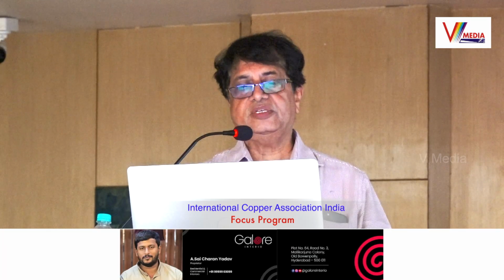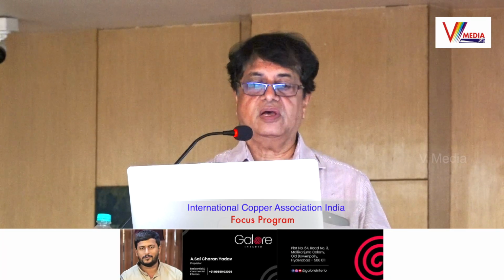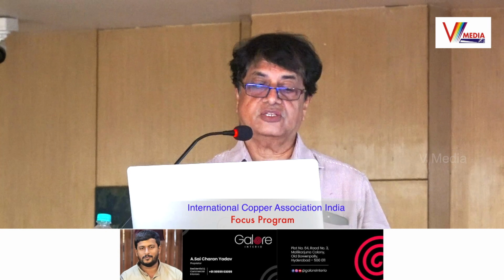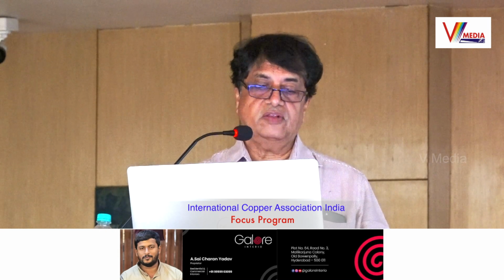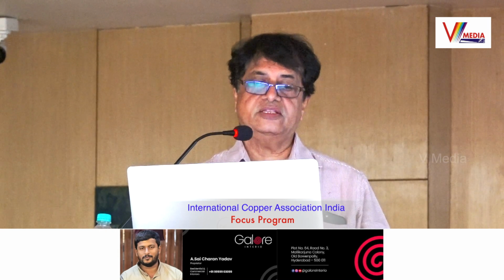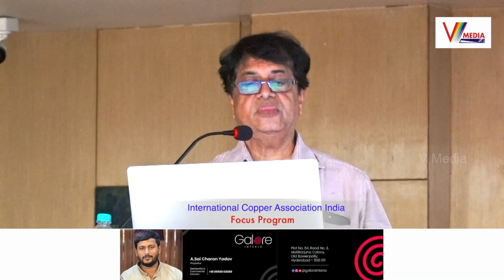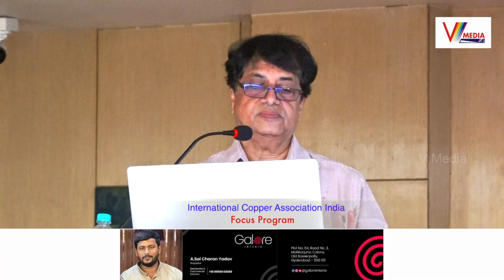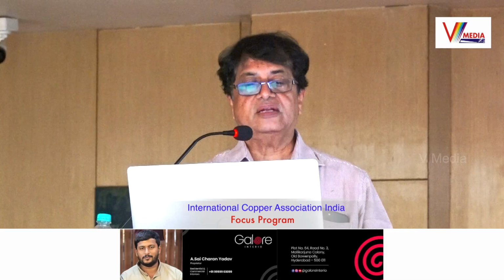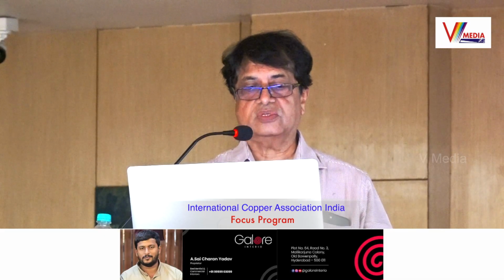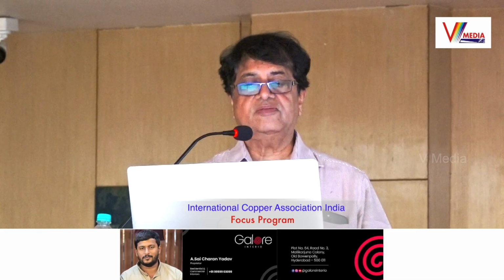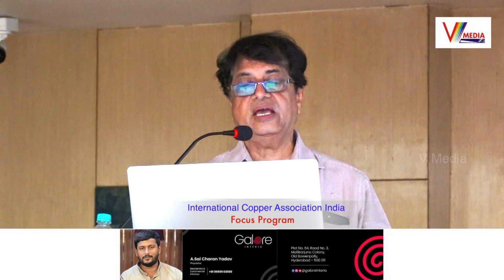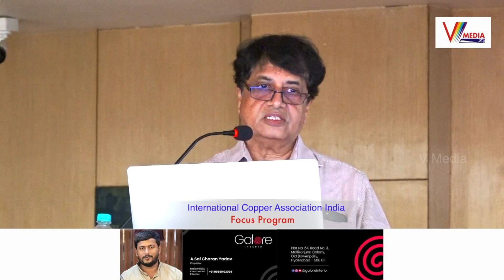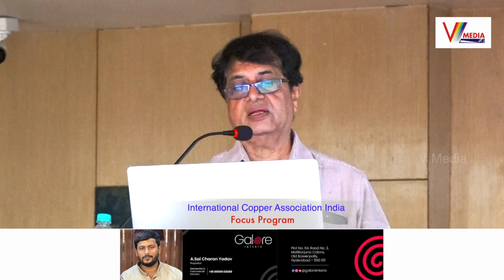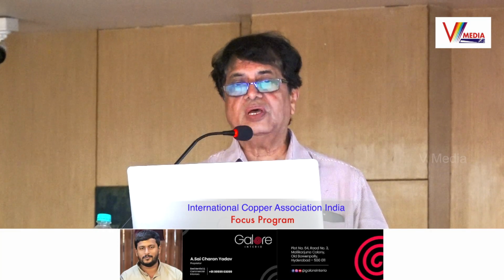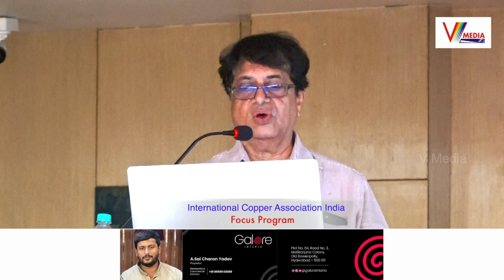There are some other requirements in respect of oil-filled transformers, such as how the room of that transformer should be designed. Here is the sill which is shown. If the oil drains out, it should be contained within that building, so the threshold of that building should be at such a height that the oil may not pass outside. These are the different pictures given in the standards, and the draining arrangement, how it is to be done. Again, this point comes in the purview of the architect. In accordance, he has to allocate the spaces and locations for all these things.